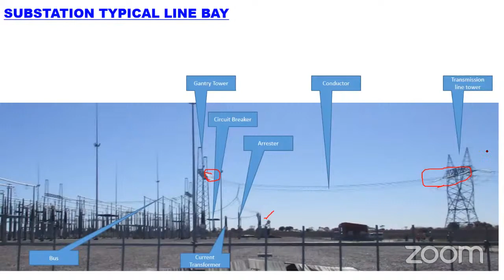Okay, a further closer view of the equipment. This is the circuit breaker. Then the conductor is connected to your current transformer, then the disconnector, then the bus bar. So you can say it is typically a line feeder or transformer feeder. These are the components involved. This component has a structure, and you can look at the person. If he is standing, it will be safe, 2.4 meters above ground with the help of structures. So in the design of substation equipment installation, there is a design of structure and foundations below ground. Then above ground, there is the equipment. This is the current transformer. This is called the structure, and this is the equipment.